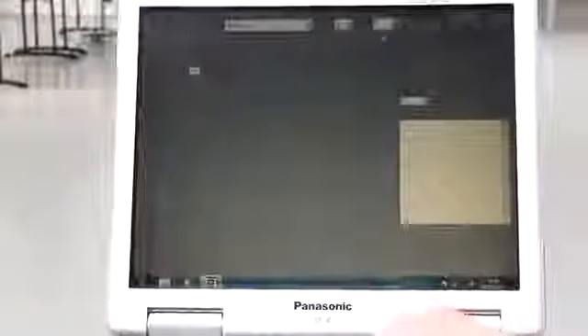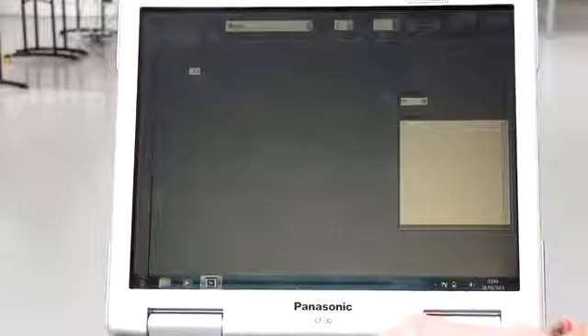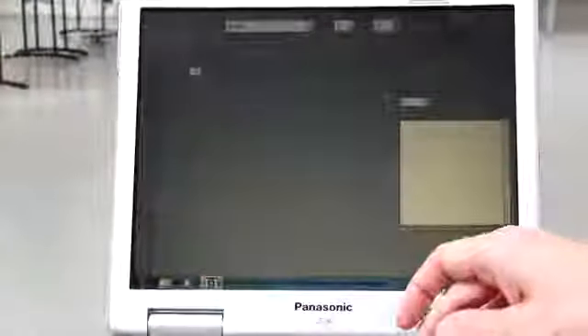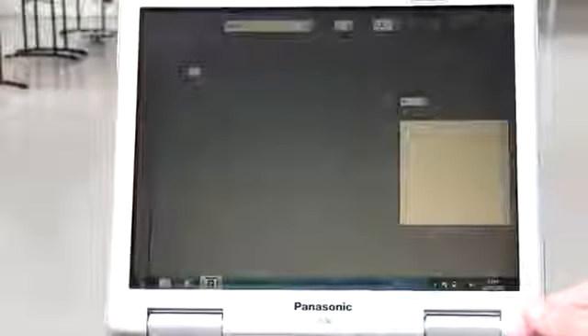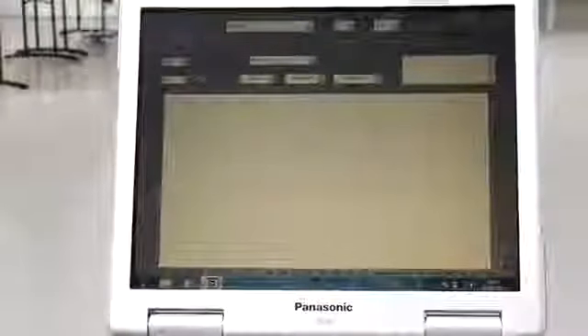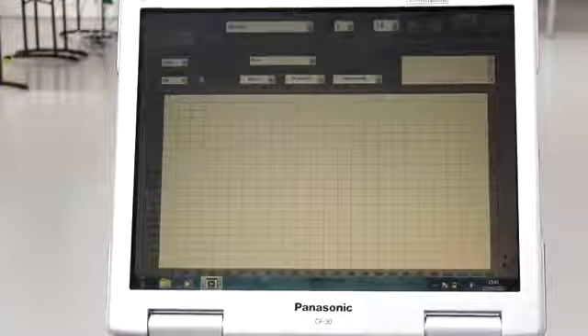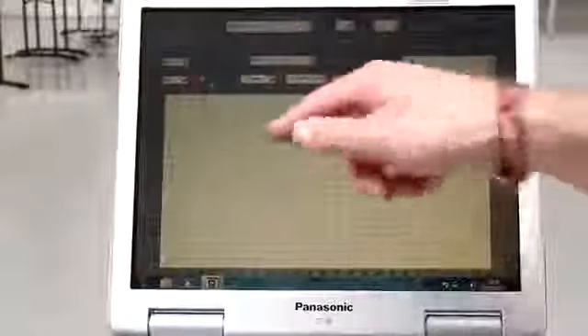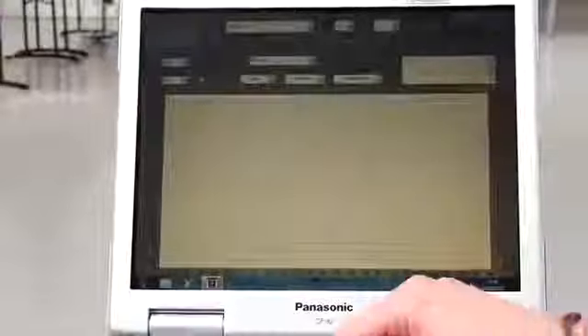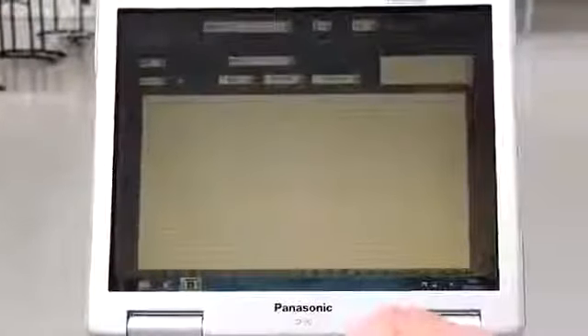When we're happy with the tank diameter, we then enter the plate number that we are going to scan first of all, using the row convention. So row 1 dot plate 1 will be the first plate we inspect, and then we press return. We are then returned to the plate screen as shown. In the plate menu, the most important thing to set is the dimension of the plate. In this case, 1200 millimeters by 600.